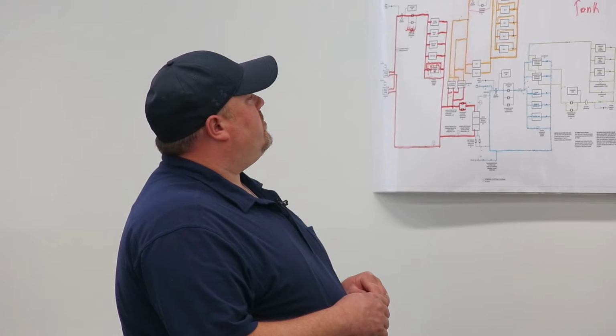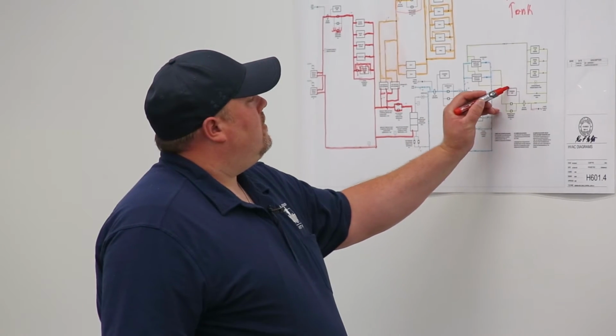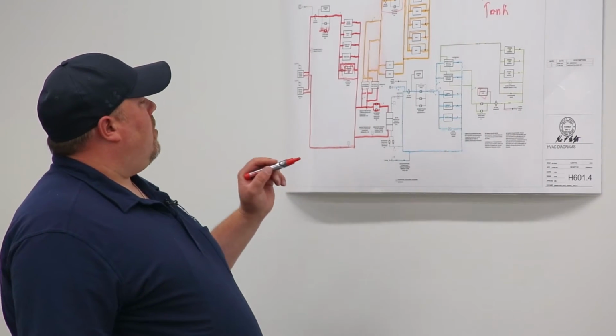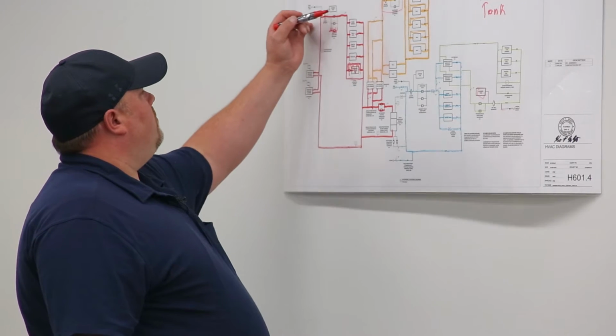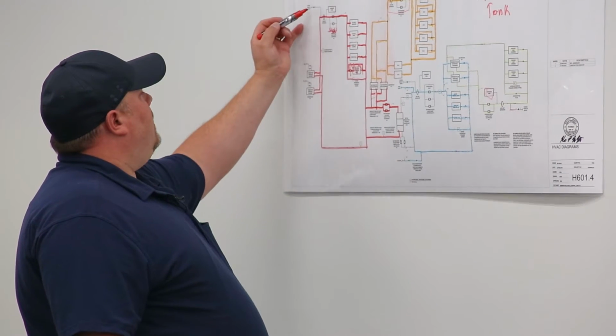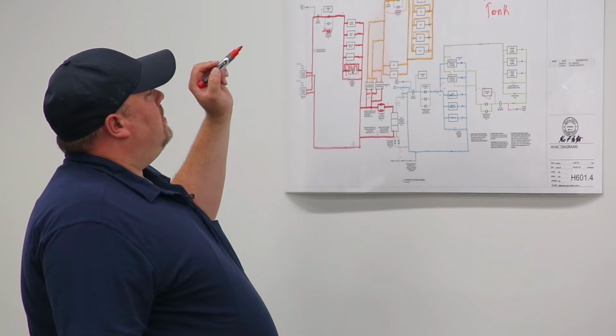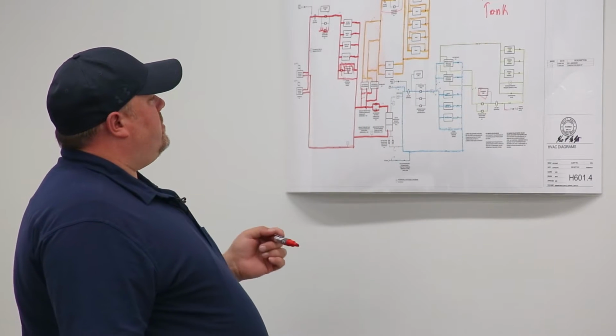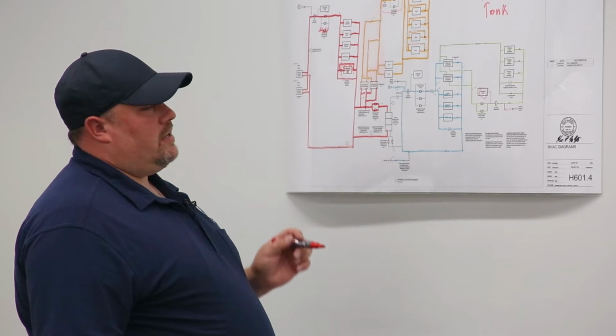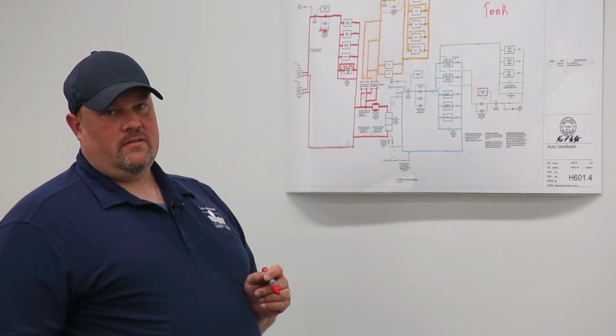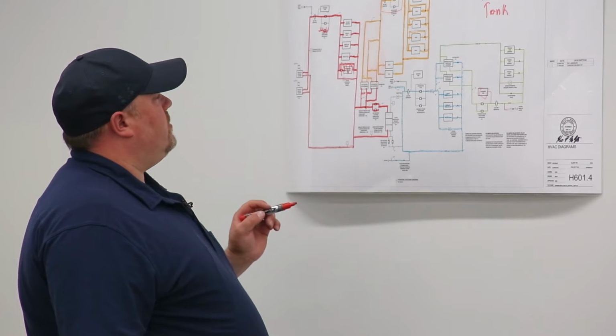With the makeup water feeds? Okay. And every other closed loop system in this building, being our processed chilled water loop, has a system makeup water feed and its own expansion tank, as well as the heating closed loop expansion tank and a system makeup water feed. And those consist of the soft cold water from the building. So our makeup water feed's all soft.